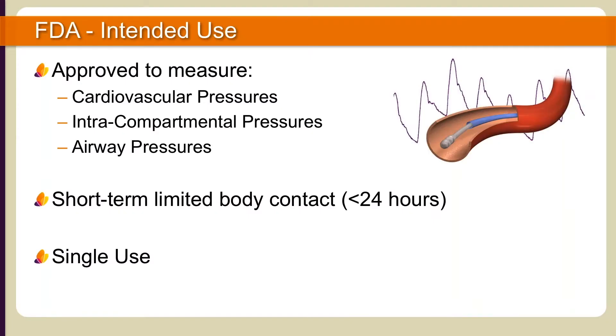Moving on to the FDA intended use: the Microcath delivers true high-fidelity pressure data for deeper insight into cardiovascular function. Although primarily known for its use in cardiovascular applications, Millar has recently expanded the Microcath indication for use to include measurements of intra-compartmental and airway pressures of the human body.